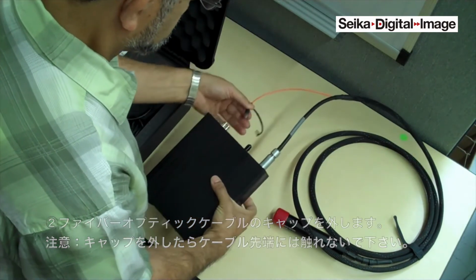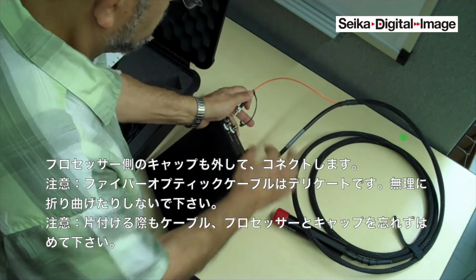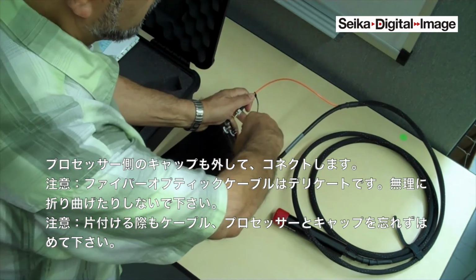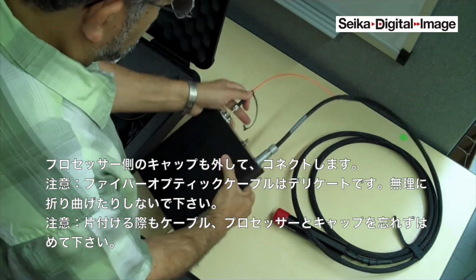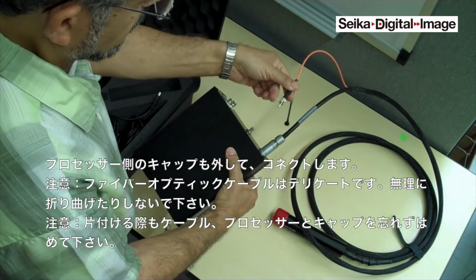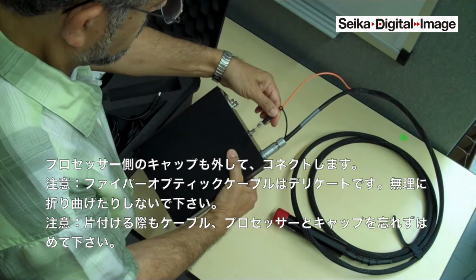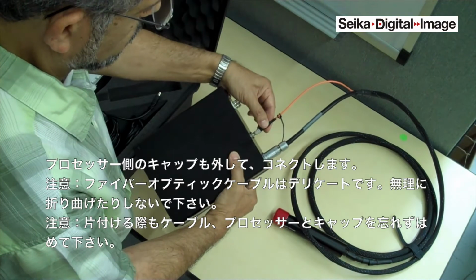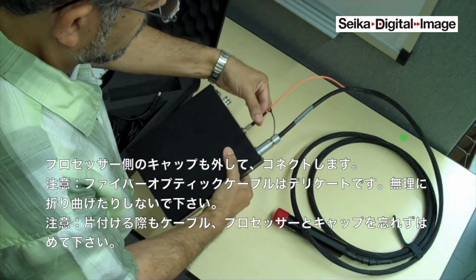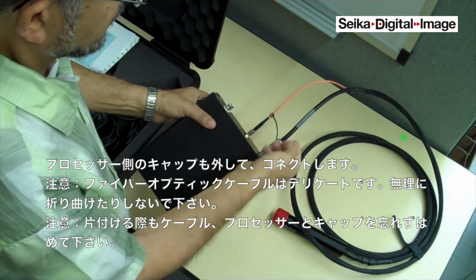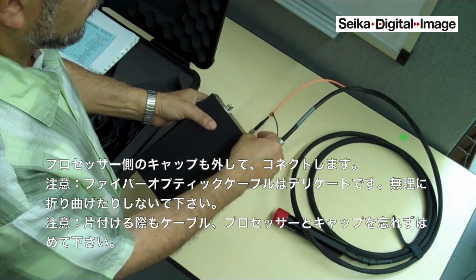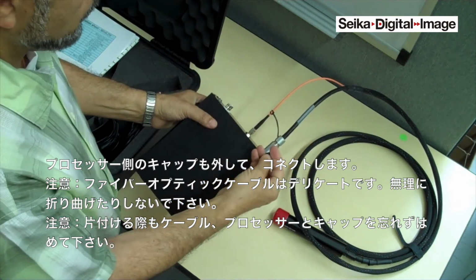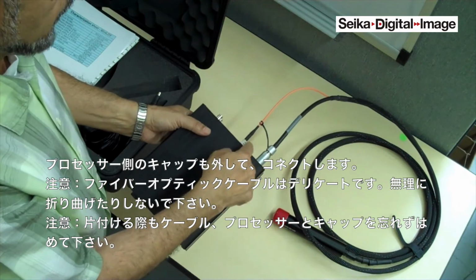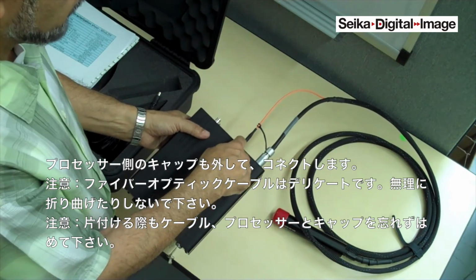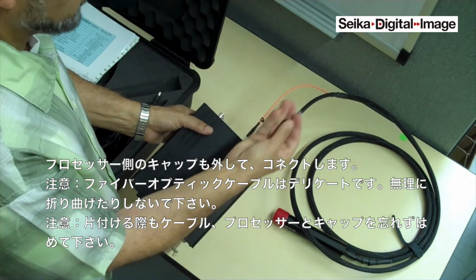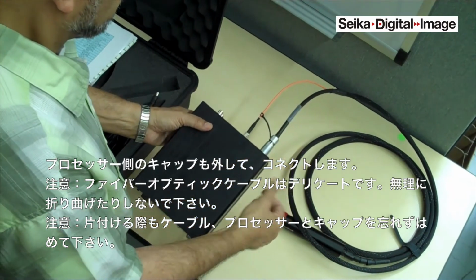And then on this other side, on the receiver side, there is a cap on the detector that you need to take out. And there is a key on the fiber that you line up with a notch, and when it goes in, you can lock it up and it's firm. When you take it out, please put back the cap on the receiver and also on the fiber end. While in the lab, leave it connected for as long as you need, but when you disconnect it, make sure you put back the cap.